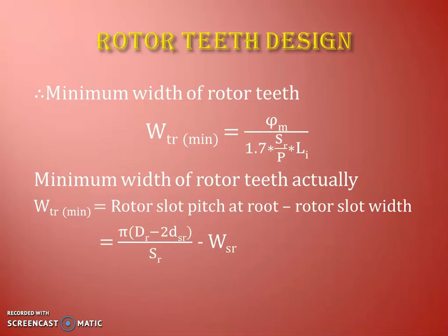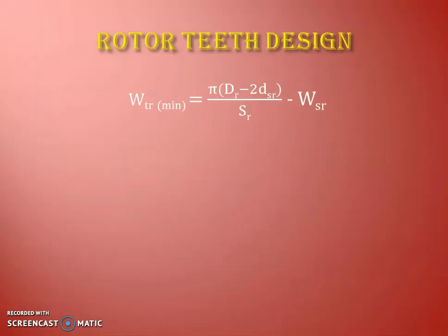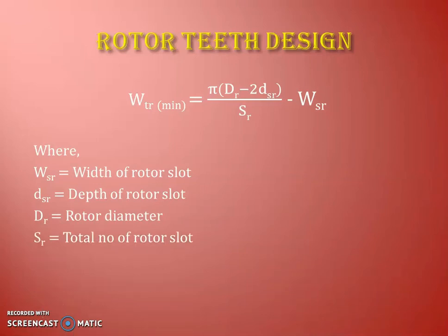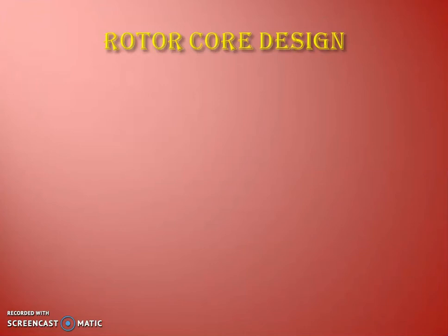The rotor slot pitch is pi times (rotor diameter dr minus two times depth of rotor slot dsr), divided by the total number of rotor slots SR. Minimum rotor teeth width equals that slot pitch minus the rotor slot width (wsr). So based on this equation, we can calculate the minimum width of the rotor teeth, where dsr is depth of rotor slot, dr is rotor diameter, and SR is total number of rotor slots.